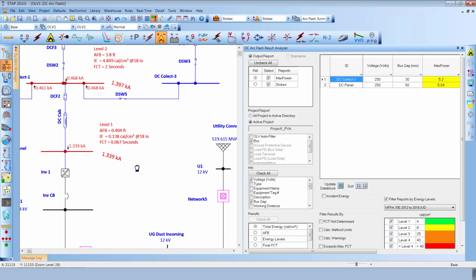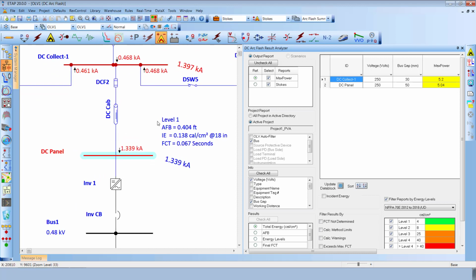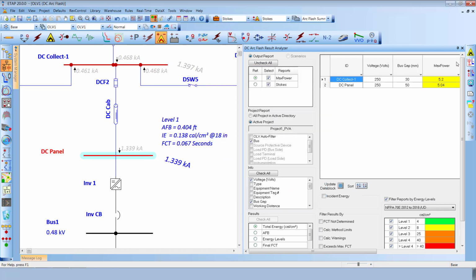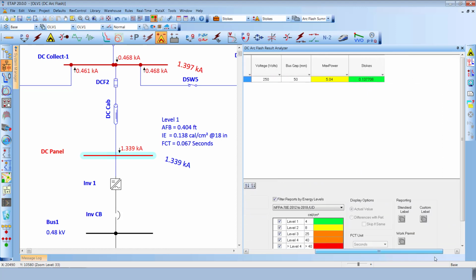have given a higher arcing current to deal with, which could obviously give a faster operating time in this particular condition. The overconservatism of the maximum power method can still be projected in this case by removing the 2-second rule. So for the same DC panel location, the Stokes method still remains the same on the fault clearing time even after removing the 2-second rule. The arc flash analyzer can still show the selected elements from the one-line diagram to filter out the results on the panel as seen here.